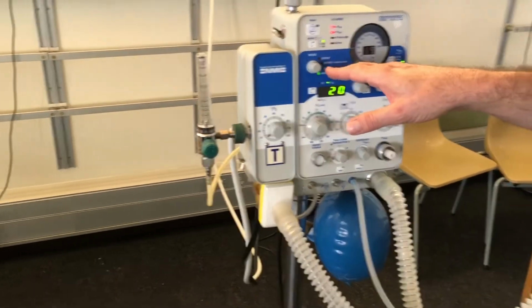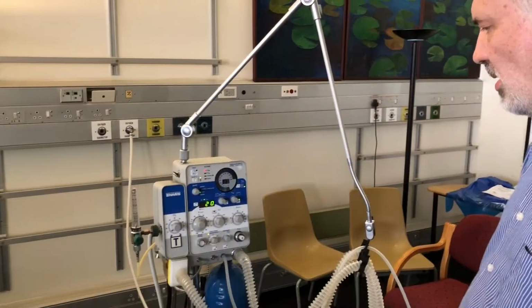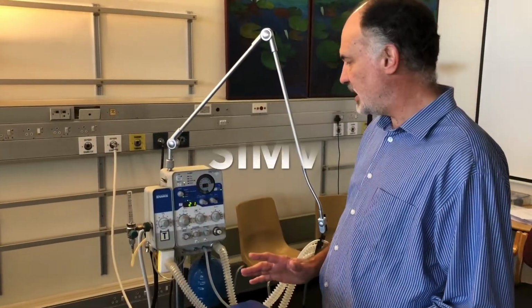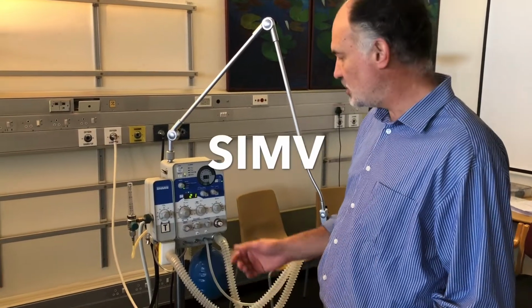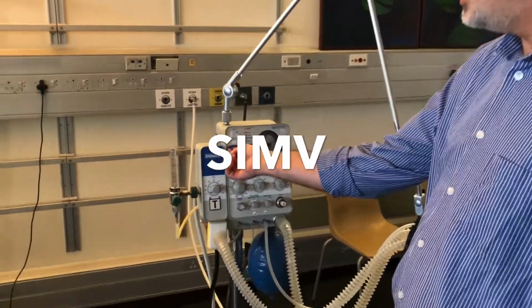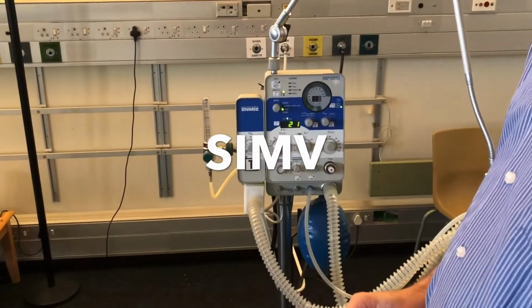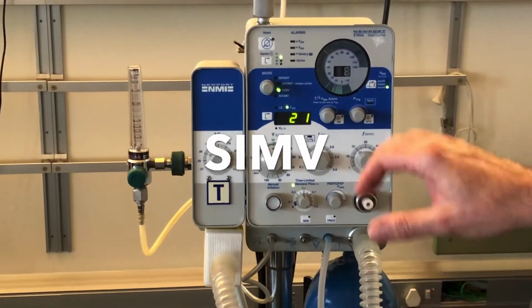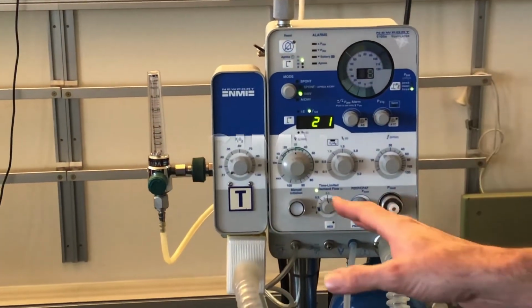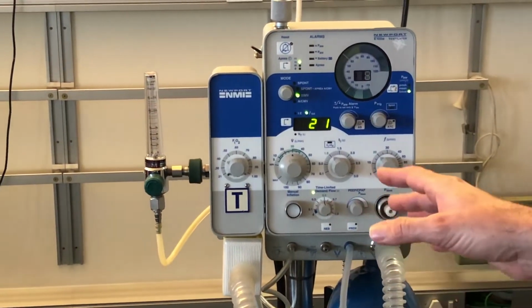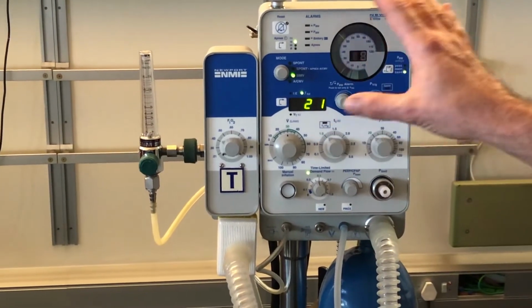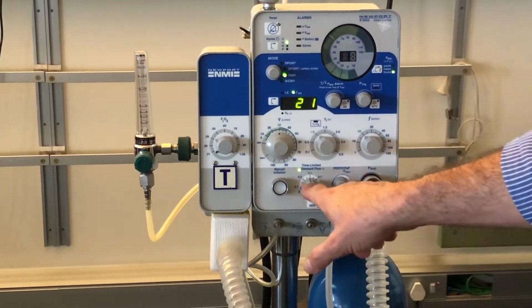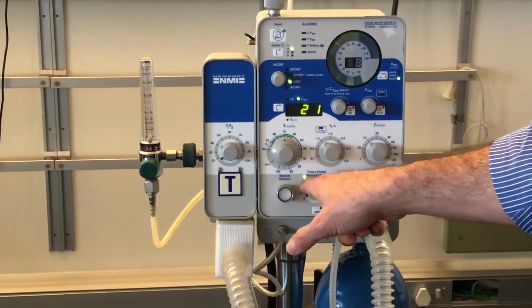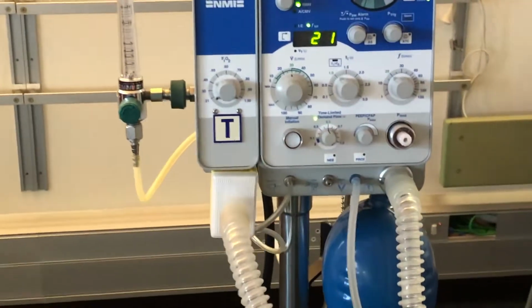We're now going to leave assist control ventilation and we're going to go to SIMV. We're going to move on to setting SIMV now on the machine. So I'm going to switch the mode selector from assist control to SIMV. And really all of the settings that I discussed with you that were relevant for assist control are all active in SIMV. But you will see now that the little light has come on next to the time limited demand flow.